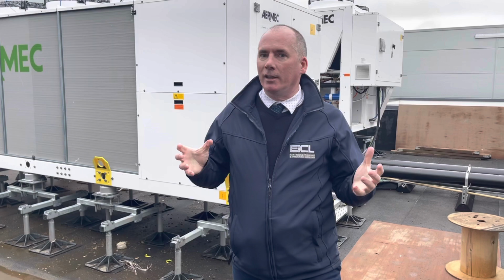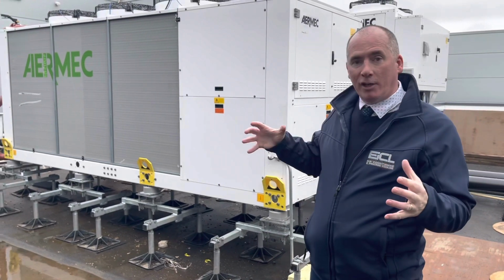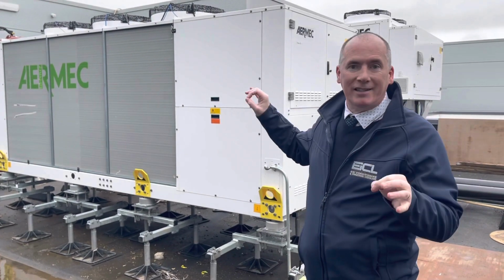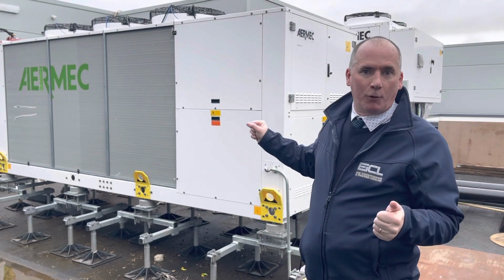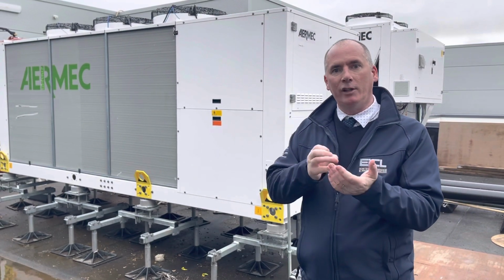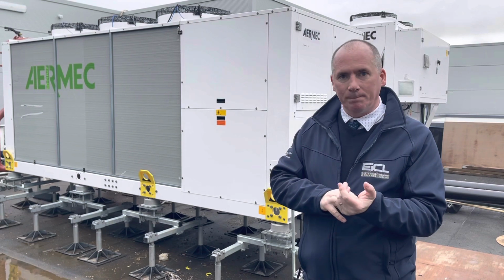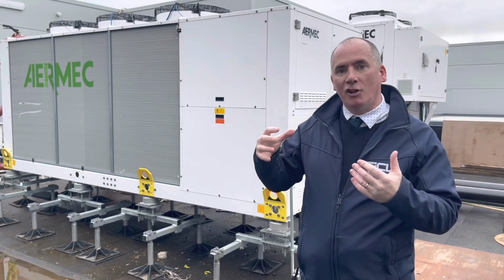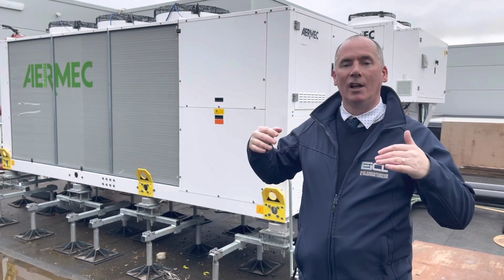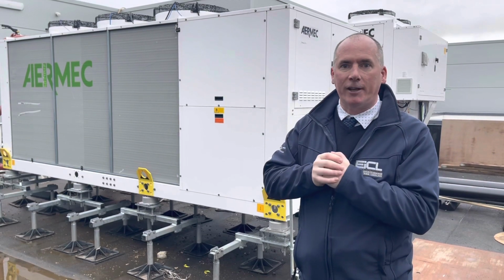So what we have here is basically a combination of lots of different technologies. Firstly, we have an NRP, it's the Aermec multifunctional heat pump, so it can do heating only, cooling only or simultaneous heating and cooling, which is really good because obviously the logic there is when you have simultaneous loads we're more than doubling the energy efficiency ratio.